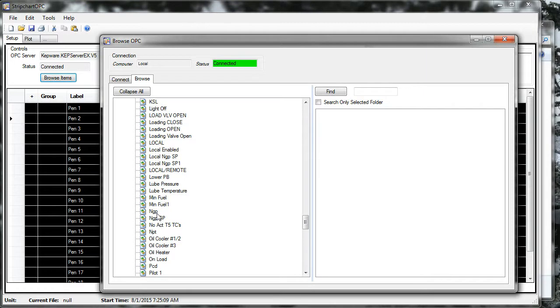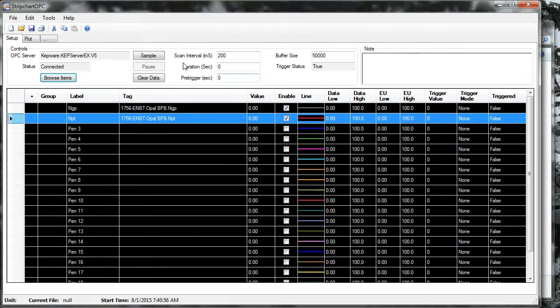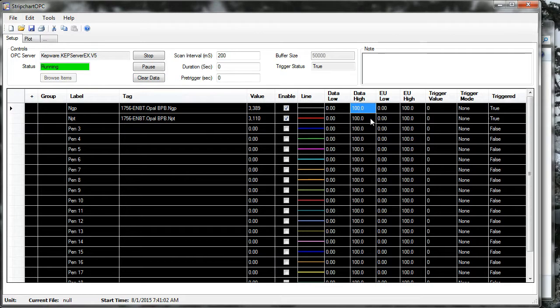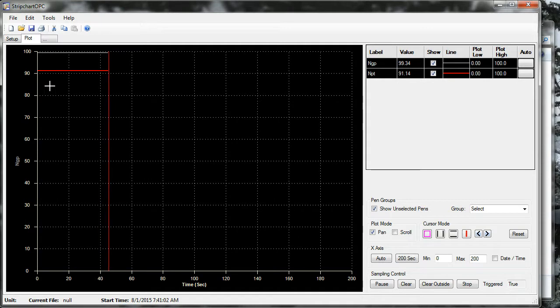Let's pick a variable and trend it. I've added a couple of variables by double-clicking them, and they show up on my pen setup table. I can then sample them. Notice the values — if you're familiar with these turbines, they don't go over 100% speed, so you'd expect nothing more than 100 here. That's because this is a raw input value, which is scaled 0 to 4095 equaling 0 to 120. I can change the scaling on the fly, and it will rescale all the data captured previously. I've changed the scaling to match, and now I see more believable values. Looking at the plot, it changed the scaling on all the data collected from time 0.